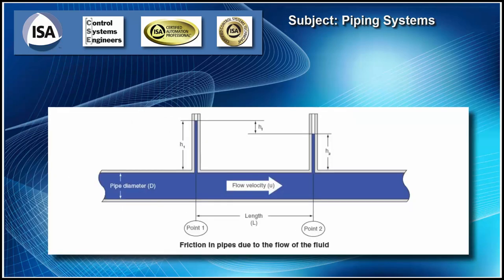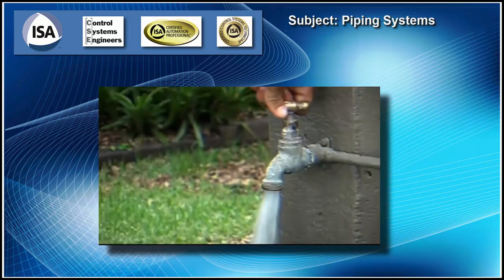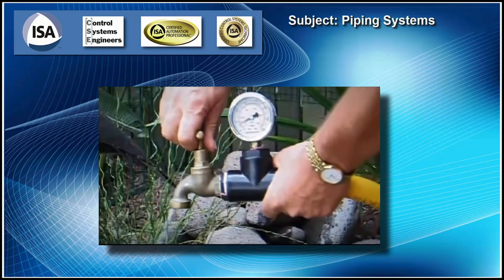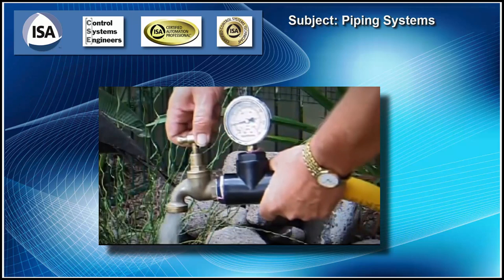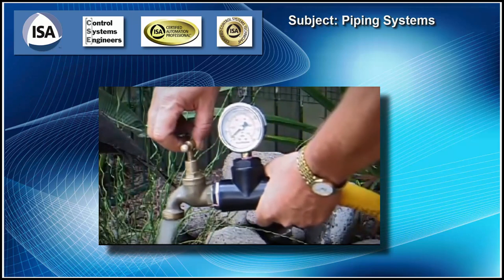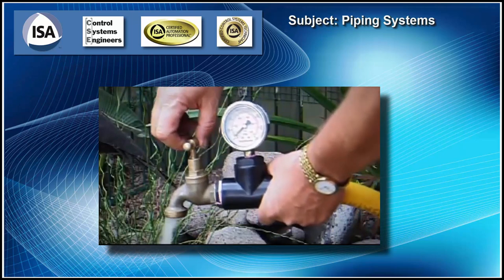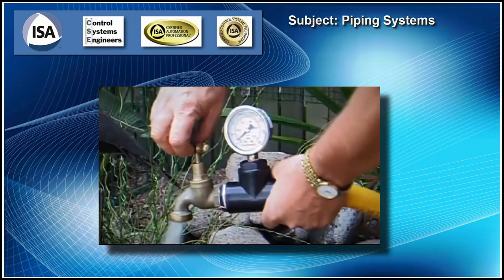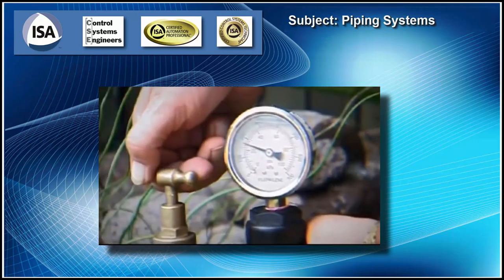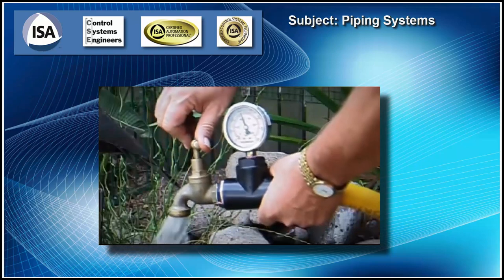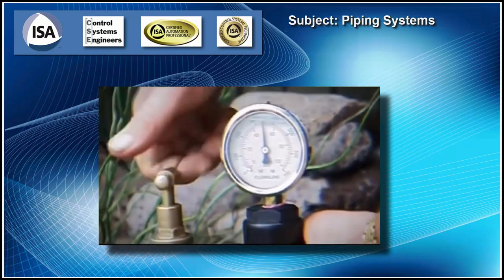So by now you should have an understanding of how pressure affects the flow rate. If you got a low potential pressure, you got a low flow rate. If you got a high potential pressure, you got a high flow rate. Okay, but remember, this is total energy in the system, potential plus kinetic. So when we speed up, even though we've increased our pressure and the water starts flowing, the potential measured in the piping system will change into kinetic. So the potential will drop as it speeds up. And that's where it looks like you have low pressure with high flow and high pressure with low flow. That's because we put more pressure on the valve to slow it down and less pressure on the valve to speed it up. That way, again, the potential will change into kinetic.